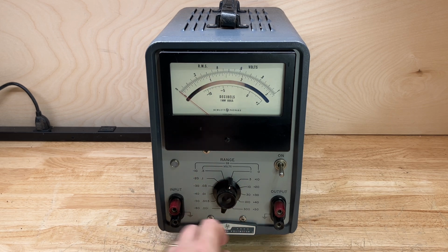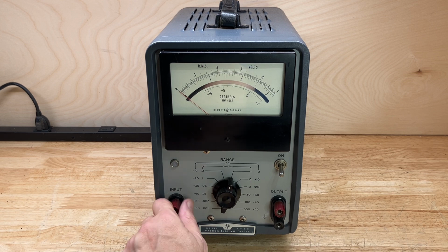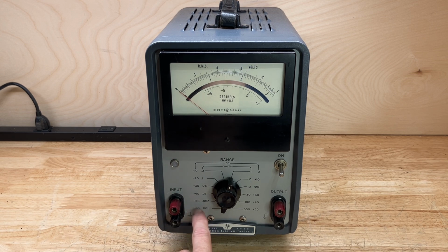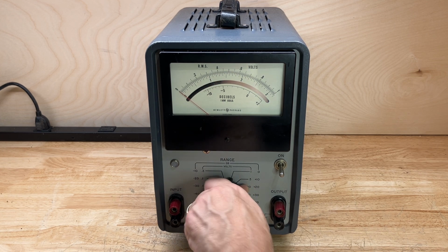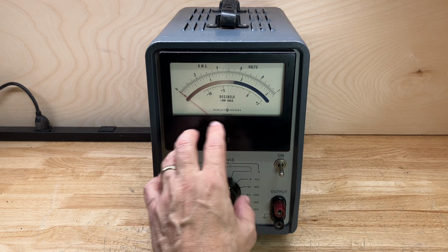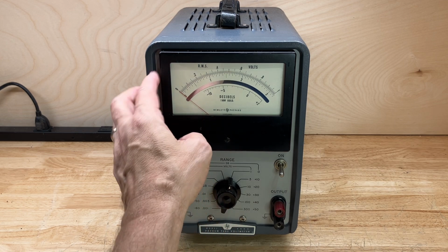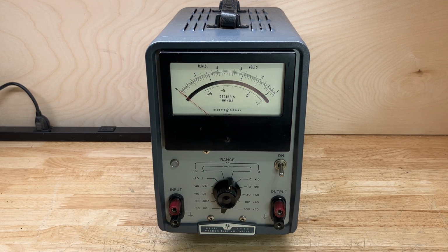I'm excited already. So this is an AC vacuum tube voltmeter, and it reads from 1 millivolt up to 300 volts in 10 dB steps, with a beautiful 5-inch individually calibrated mirrored scale linear display meter movement. The frequency range on this instrument goes from 10 hertz to 4 megahertz with a 10 megohm input impedance.